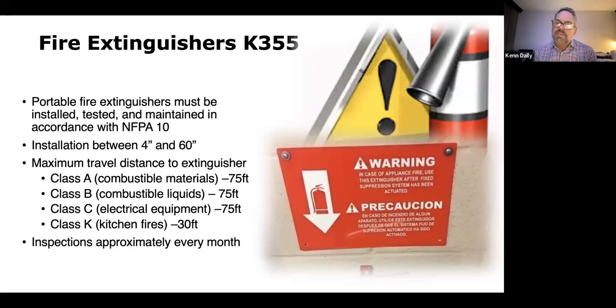That's all under NFPA 1 and NFPA 10. Then monthly, you're hefting it, taking it off the wall, picking it up, shaking it, feeling the contents, and making sure the tag is present. You're also making sure that the needle is in the little pie-shaped green space on the meter reading. And for the K-type extinguisher, the red warning sign above it needs to be present as well.